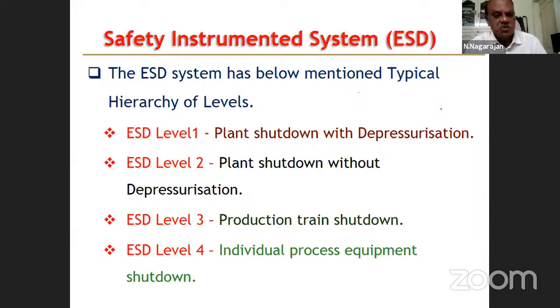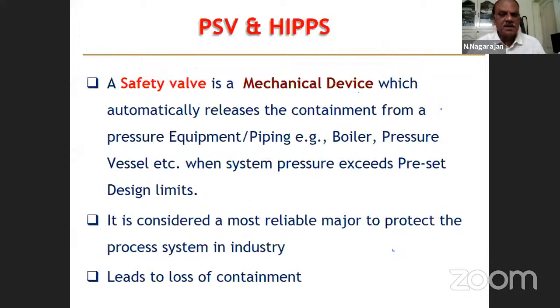Otherwise, ESD level 2. Level 3 is for a small unit, one production train. One unit is being isolated and shut down. ESD level 4 is when one equipment is in problem, one column or one vessel is in problem. These are called individual process equipment. This is of minor nature, ESD level 4. And now we see PSV and high integrity pressure protection system.